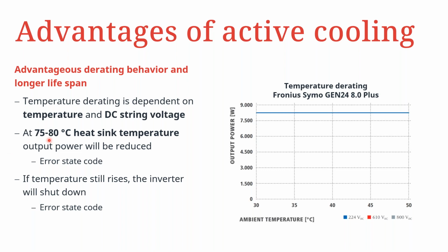However, if the heatsink temperature goes to about 75 to 80 degrees Celsius, then the inverter output will be derated, and the state code related to heat will be sent to SolarWeb. But if the temperature continues to rise above these 80 degrees, then the inverter will shut down and a state code will likewise be sent. Here we can see an example of an operating graph relating to the nominal power rating of the inverter, which is in this example a GEN24 Plus 8.0 kilowatt, and the ambient temperature. We can see here that the inverter is able to give you full output even up to about 50 degrees ambient temperature.